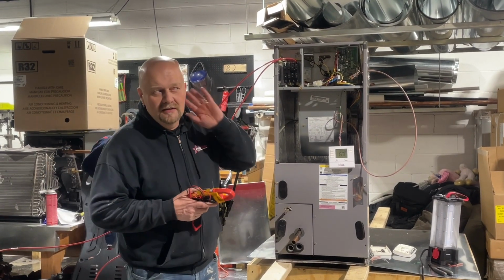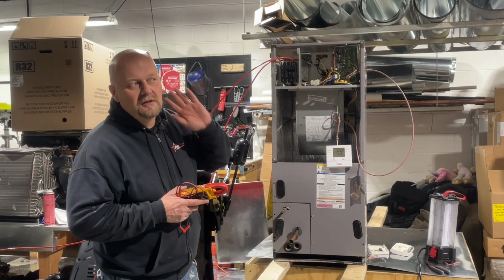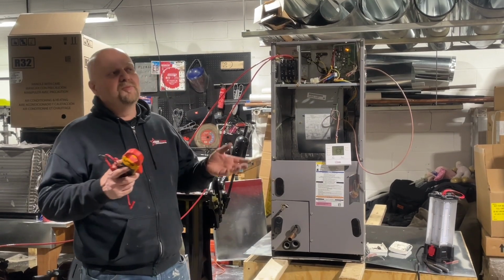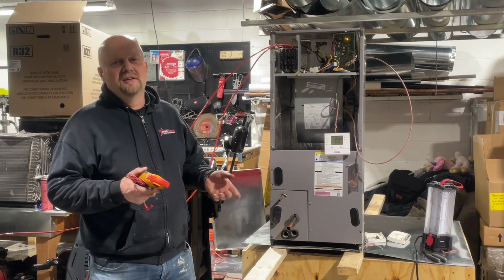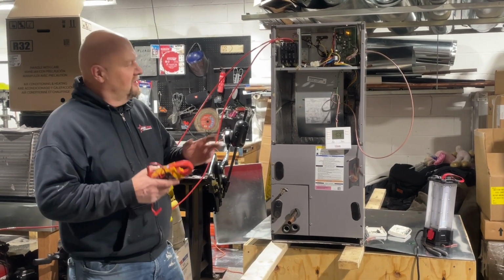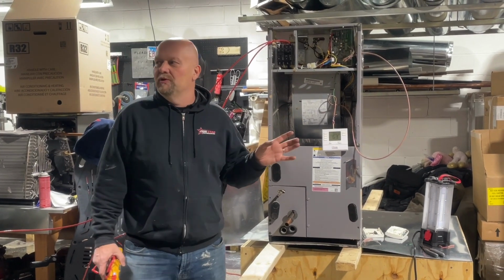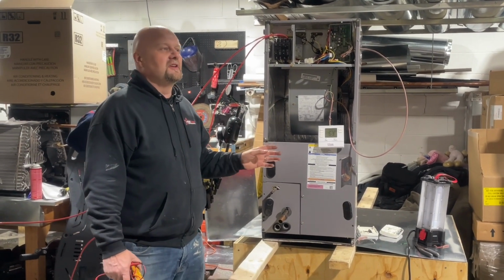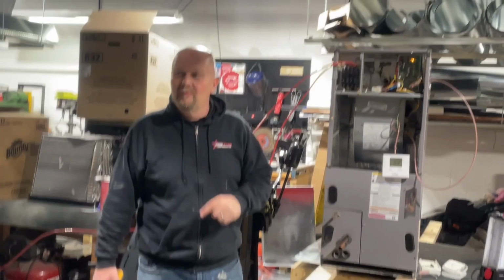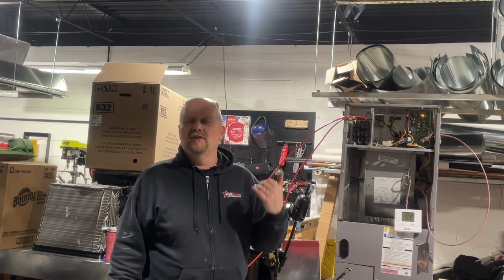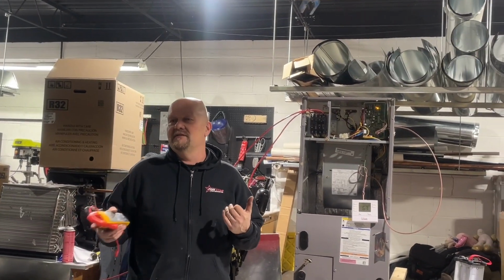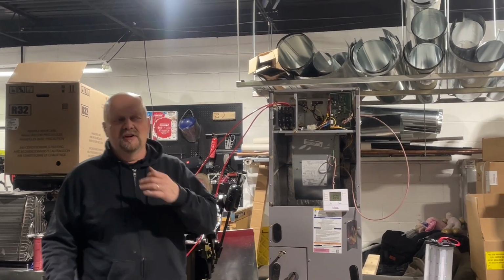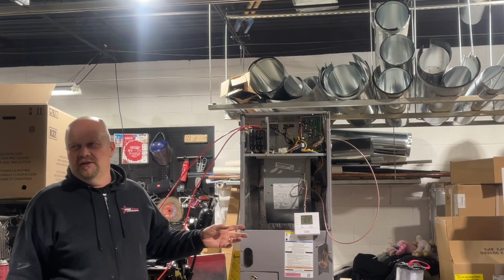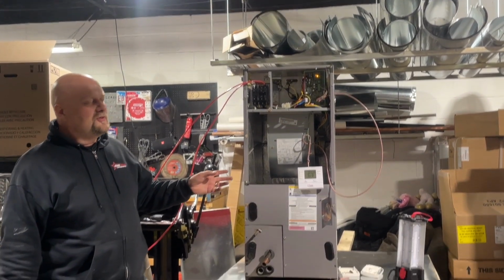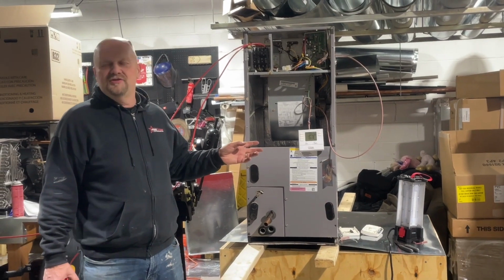9,470.5. Say that again. 9,470.5. Okay, so that means 9.4 kilowatts. So that's the actual heating output of this unit. So is that a 10K or 8K? That's a 10 kW. Typically, they're going to be a little bit lower than they say they're rated for. That's because they're rated for higher voltage. So when they rate these units, they rate them at like 240, 208 volts.